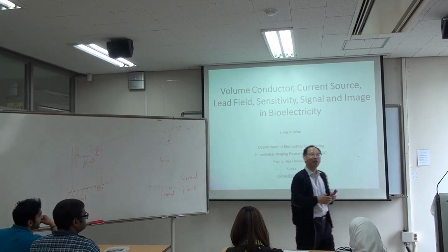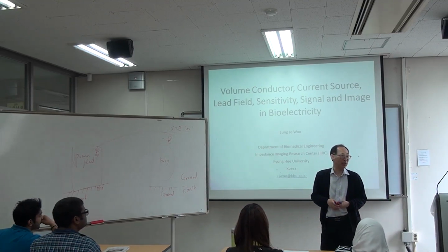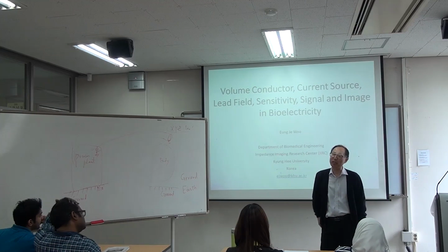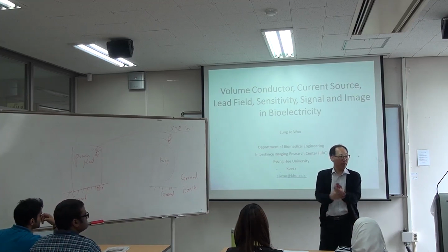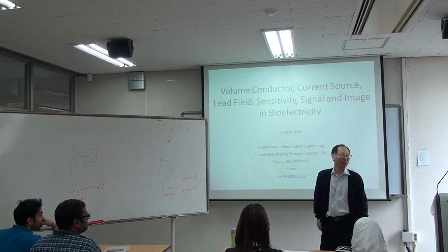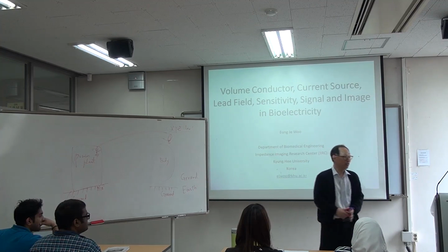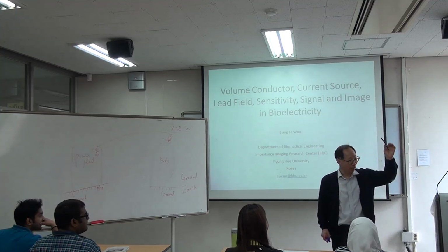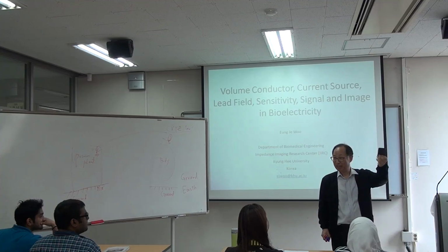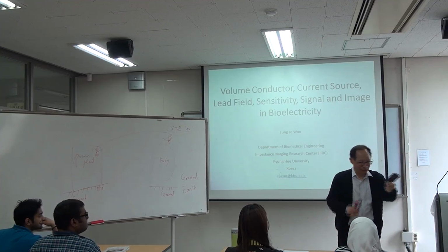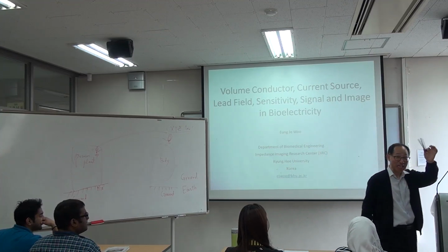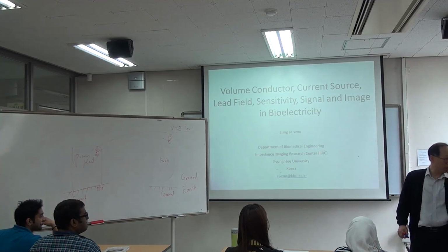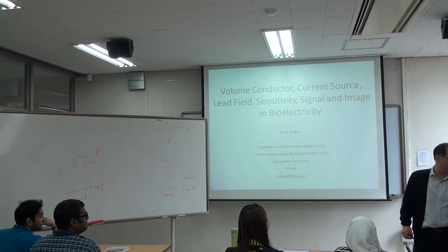When we make a medical device, or a battery operated device like a smartphone or health band or something like that, are they grounded or not? Yeah, we have a smartphone here. I'm holding it. Is this grounded or not? It is not grounded. Where is the connection? No, it is not grounded. But it's working perfectly fine.